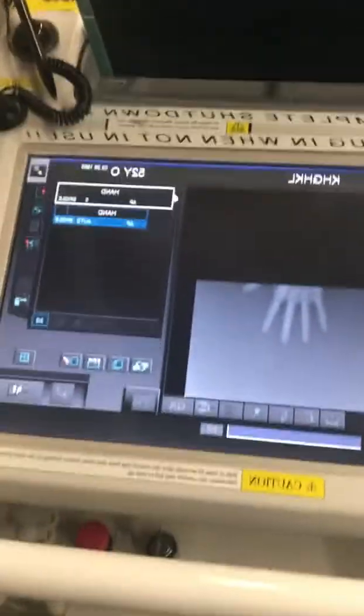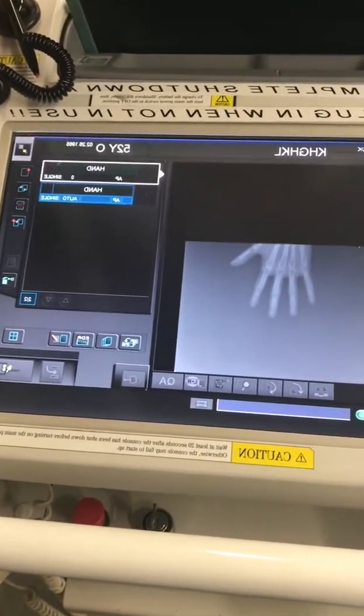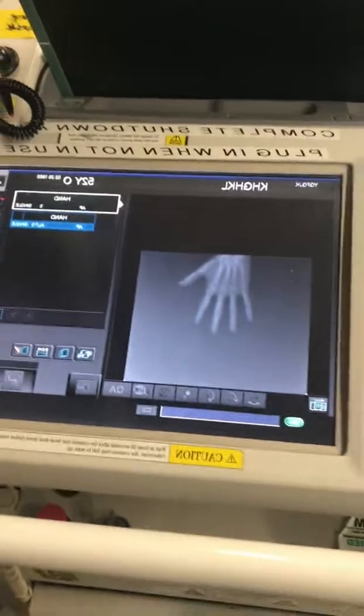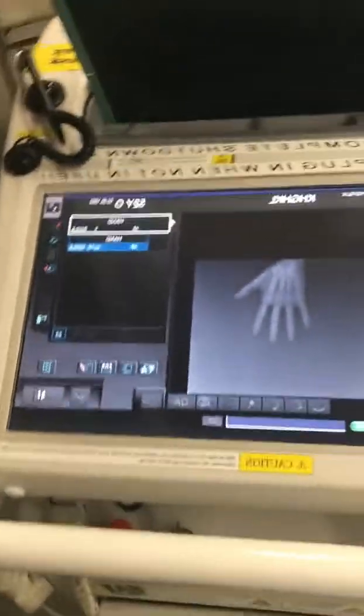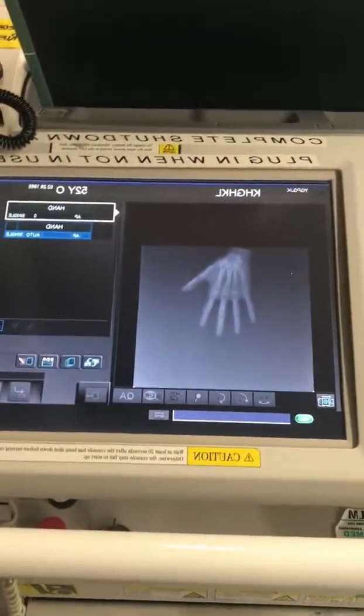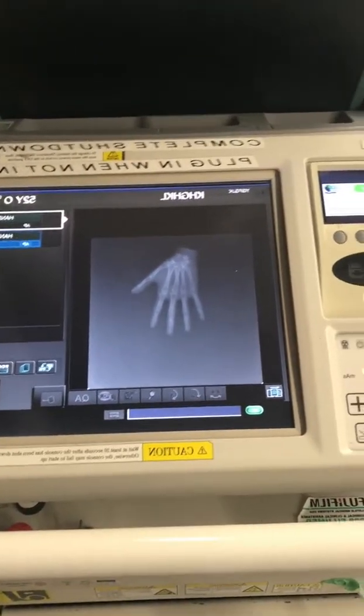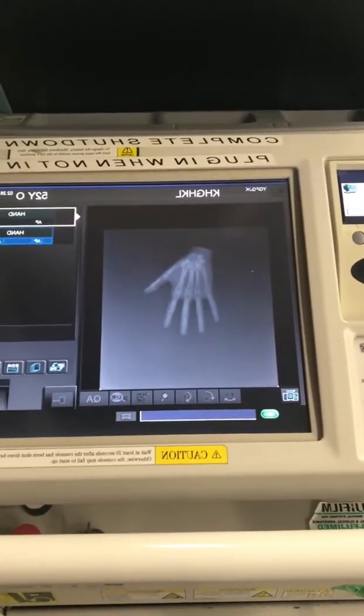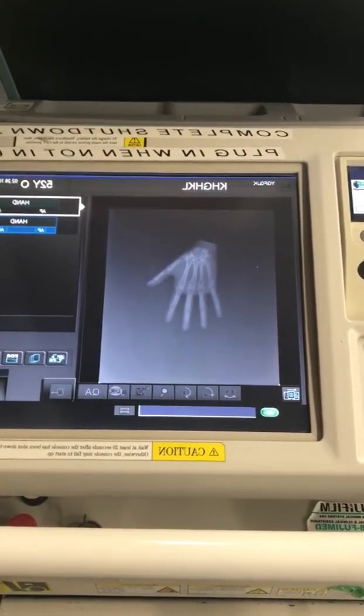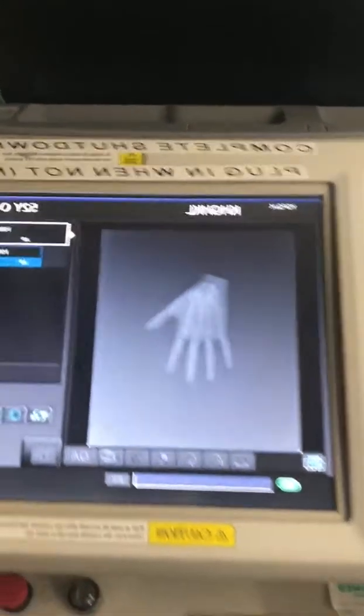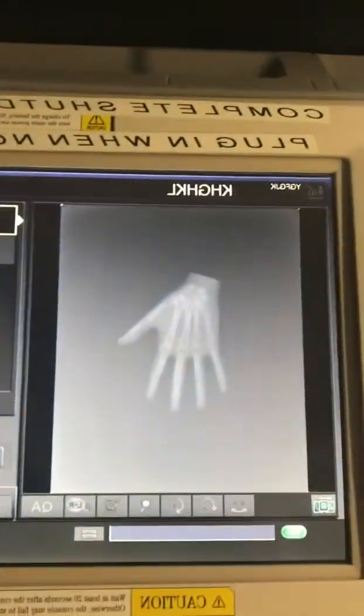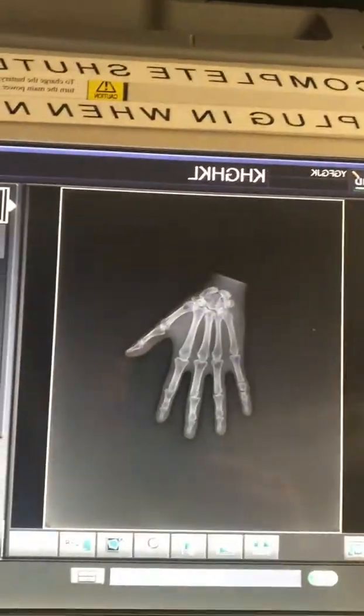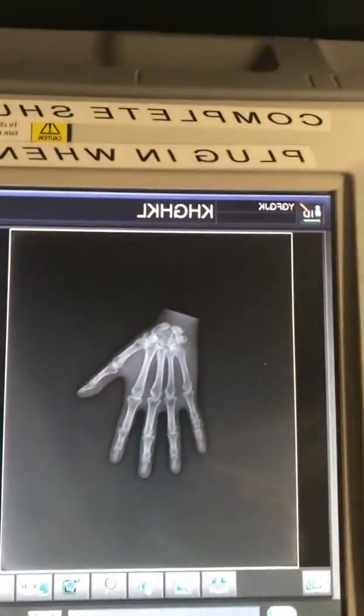That is again the button that we're going to push for the X-ray - X-ray just normal like any other one. Software on here is the same as any Fuji CR. At this point, this is generally meant to send to a PACS, which would be set up with the network to automatically send over there.